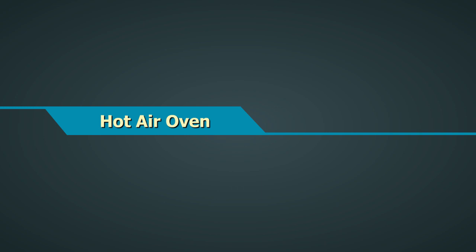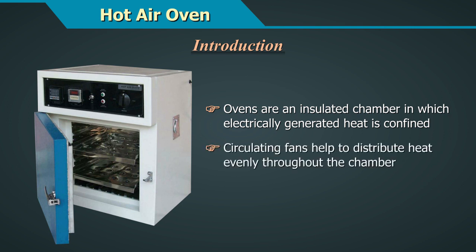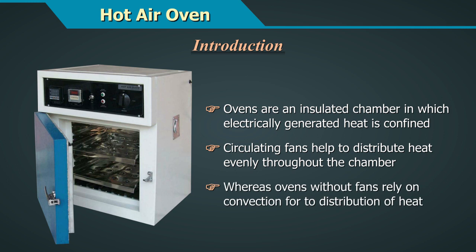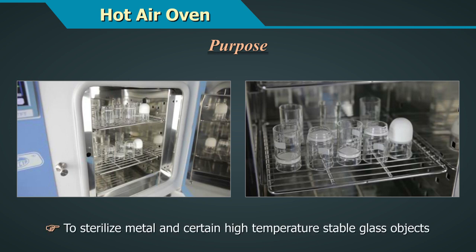Hot Air Ovens are an insulated chamber in which electrically generated heat is confined. Circulating fans help to distribute heat evenly throughout the chamber, whereas ovens without fans rely on convection for heat distribution. They are used to dry glassware and to sterilize metal and certain high temperature stable glass objects.